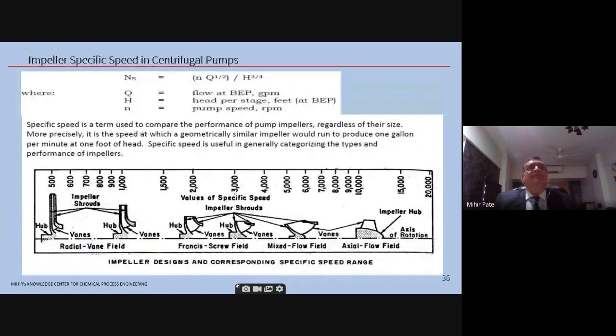Now, impeller specific speed in centrifugal pumps. The process engineer normally does not look into this, but for your information, I have kept it. Depending on the type of pump, you see the specific speed is varying, okay, with the axial pumps on the right hand side. This is not important, so don't worry about this too much. The next slide is important, which I'll explain to you also. So NS is an indicator of the impeller geometry and discharge characteristics, what you are seeing just now. And the suction specific speed, which is the next slide, is important for the process engineer. We'll go to that slide now.